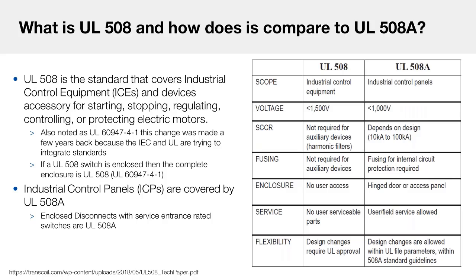And since daily I'm in contact with customers and people in the field, I have also heard of some confusion between the UL508 standard and the UL508A standard. So I just wanted to very briefly explain that the UL508A standard covers industrial control panels, meaning that these are complete panels that have a UL98 switch, so service entrance rated, inside. The UL508 is still for motor disconnects, but if an enclosed solution is UL508A rated, then it means that it has a UL98 switch inside. It's kind of confusing, but after enough practice, you can see the difference between those two. So in later slides, you will be able to see, for example, our enclosed UL98 switches have a complete solution standard of UL508A.